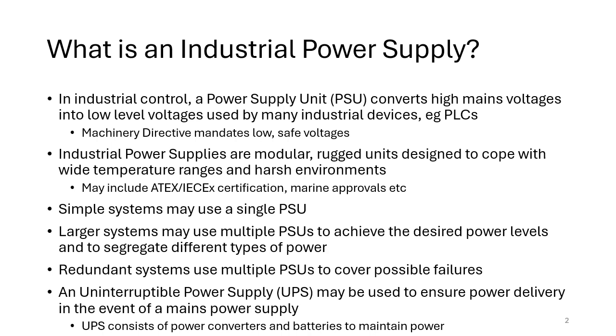In the European Union, there's a machinery directive which specifically mandates the use of low safe voltages. Typically anything higher than 40 volts gives you an electric shock risk, and higher voltages can even be fatal. So we often prefer to use 24 volts because it gives us a high degree of safety, but still provides enough current to have some noise immunity and also the current capacity to drive more powerful devices.